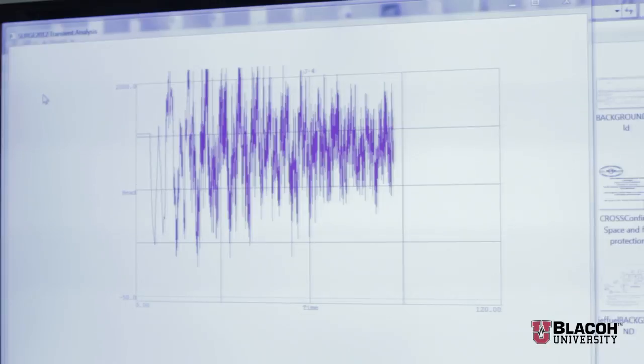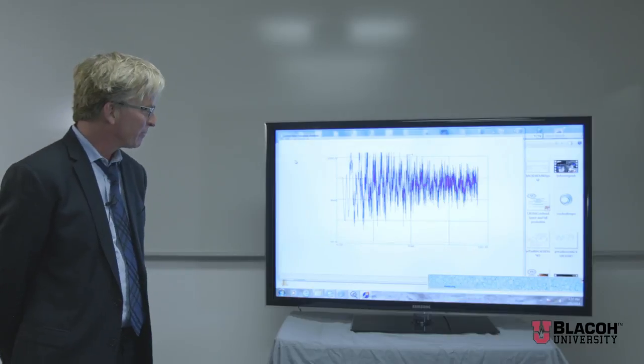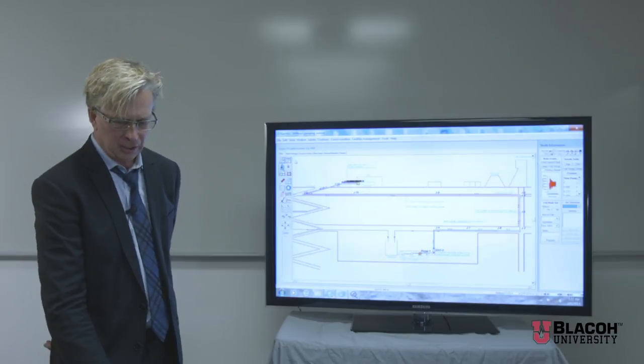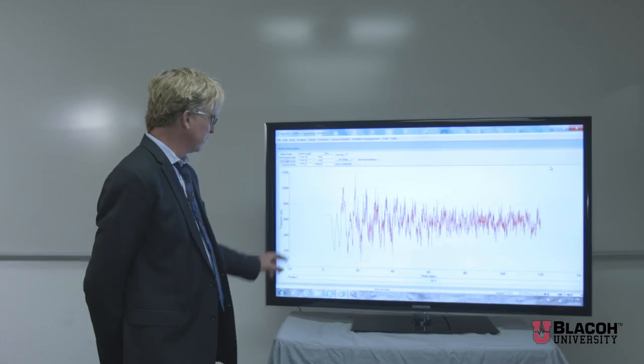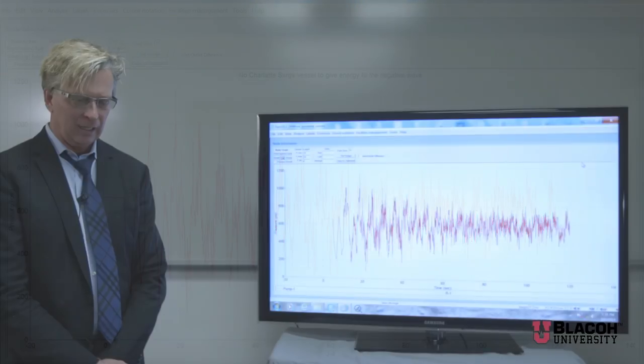Like the video I showed you with the wave oscillating back and forth, you can see the shock wave oscillating back and forth in the computer analysis. We're running the simulation for 120 seconds. The software is using Joukowsky's equation. It looks at these segments of pipe and does the calculations quite efficiently, quickly. When we started the model, there was a pause which gives us the ability to look at the system in a steady state condition.